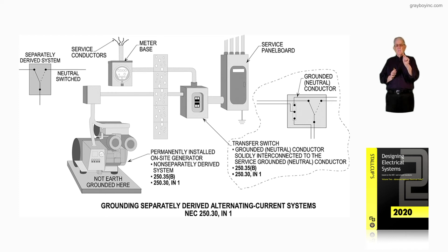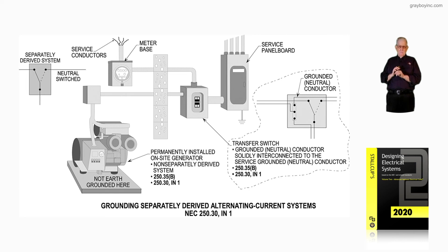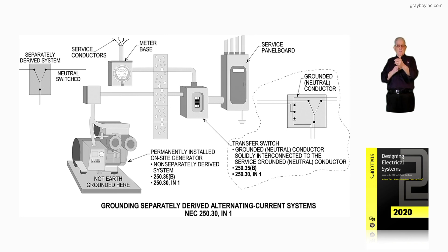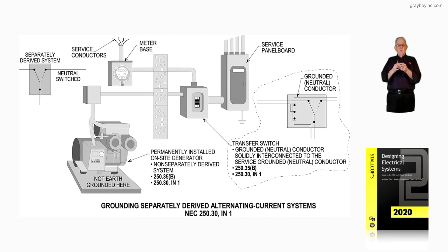But if the generator shown in this illustration is permanently installed, then under the transfer switch you have to look at 250.35A and B. Do you have an overcurrent device protecting the conductors at the generator ahead of the conductors routed over there, or under certain conditions permissible by the manufacturer, do you not have an overcurrent device at the generator? So you have to use 250.35A or B for a permanently installed generator. But 250.30 informational note 1 and 2 deals with classifying the generator as separately derived or non-separately derived. So 250.30 and 250.35 work together for separately derived or non-separately derived generators — and that's what this illustration is illustrating.